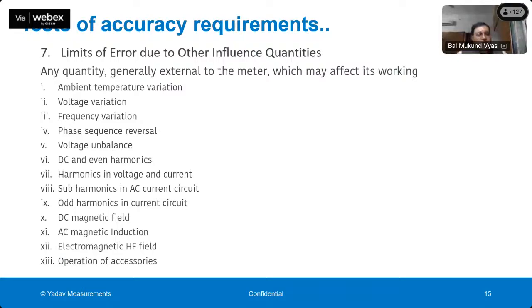Similarly, frequency can vary. Normally our frequency should be 50 hertz, but sometimes it can vary by plus minus 5%. So how frequency variation can affect the accuracy of the meter, and the limits, are specified in the standard. Phase sequence reversal is applicable to a three-phase meter. If you have a three-phase meter, then the phase sequence can be RYB or it can be RBY, and it is specified in the standard that this change in phase sequence should not affect the accuracy of the meter more than the specified limit.